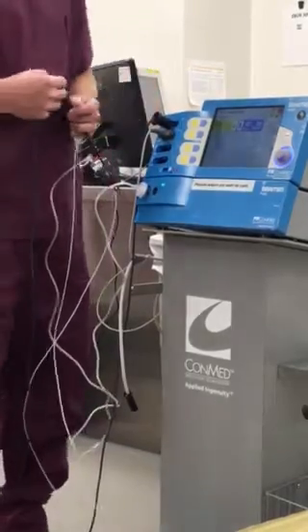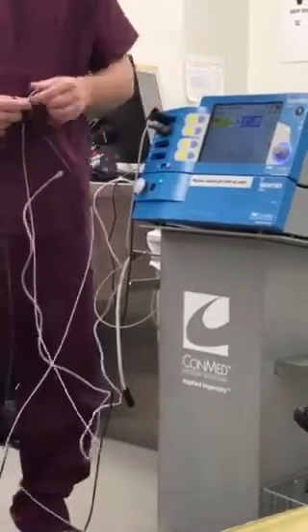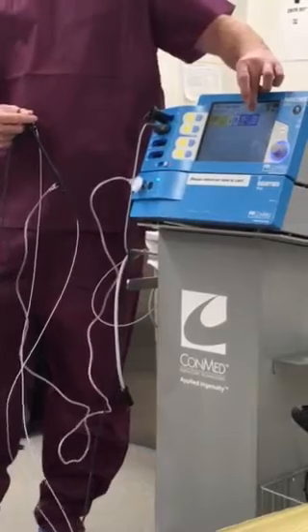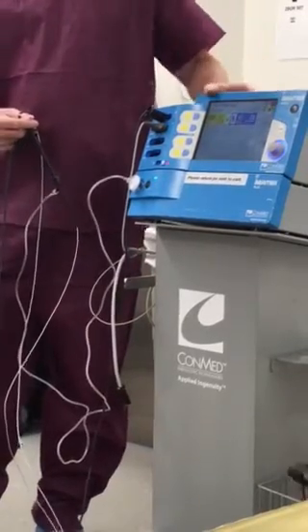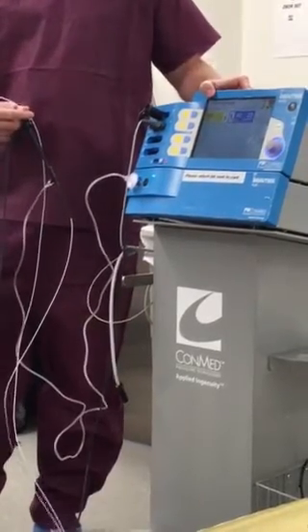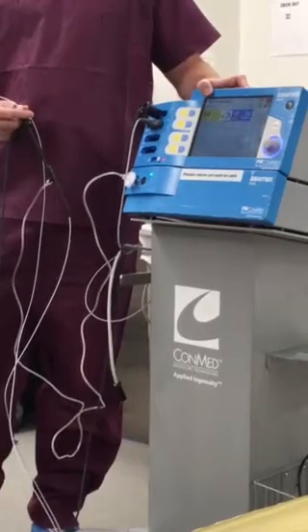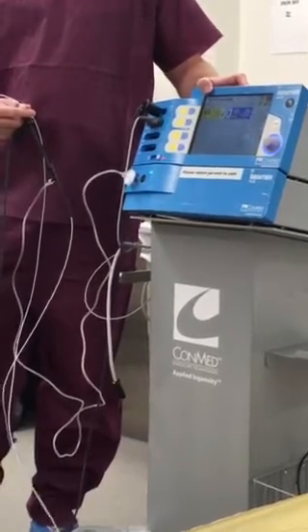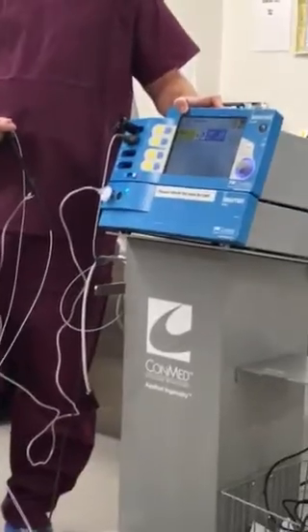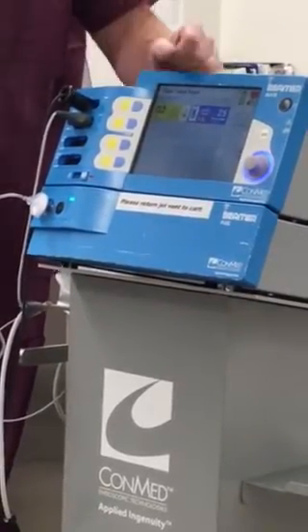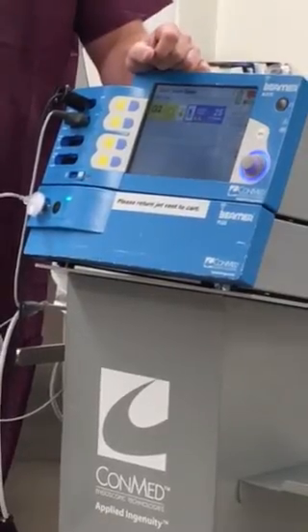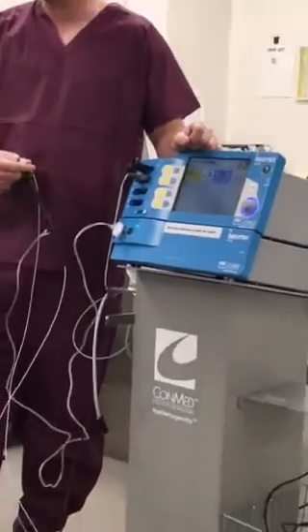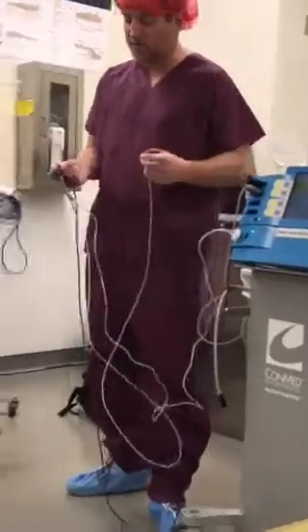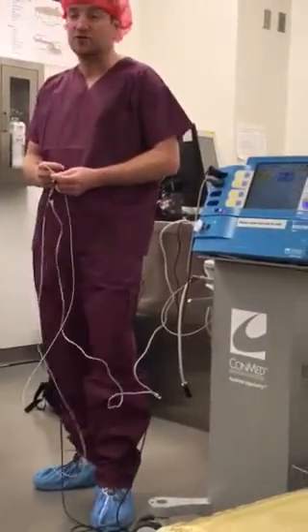Okay. So you have two main kind of outputs here. You have your energy output, which is 25 watts, and your gas output, which right now is 0.4 liters per minute. That should be okay. You can always increase it to 0.6 or 0.8. It should be enough. That's if you don't get a good beam at all, you can increase it and have a little bit more gas and get hopefully a little bit better beam out of this. This is typically going to be used for more therapeutic cases where they actually do want to resect.